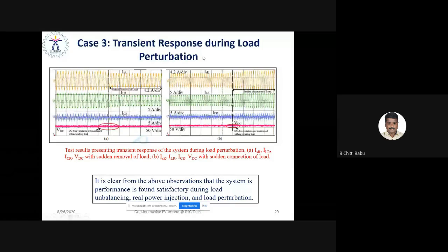So whenever there is a sudden change in load at this point, how does the inverter ensure the DC link voltage stays constant? That is what we have shown in the figure here, and here is the sudden removal of load. Due to the sudden removal of load, the load current in the R phase suddenly reduces. In the meanwhile, the current in the C phase remains the same, but the load current is largely reduced. To maintain the power flow constant, the DC link voltage is maintained constant by the outer voltage loop. So the dynamic response of the voltage source inverter with the DC link voltage control is efficient. It ensures the DC link voltage remains constant during perturbations in the load.